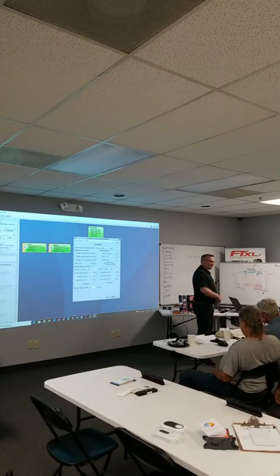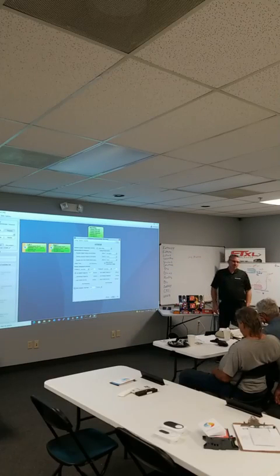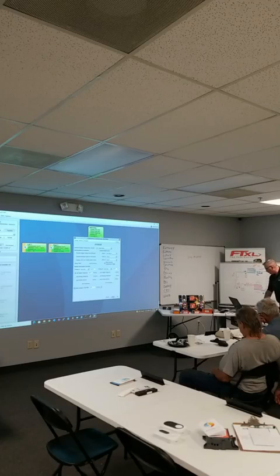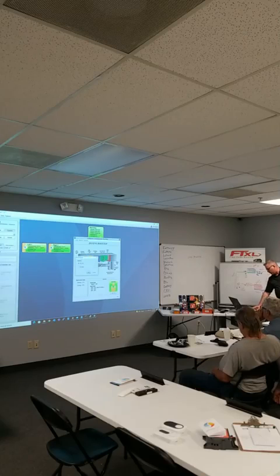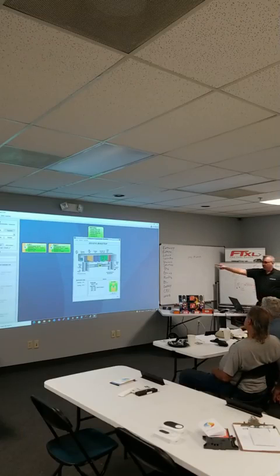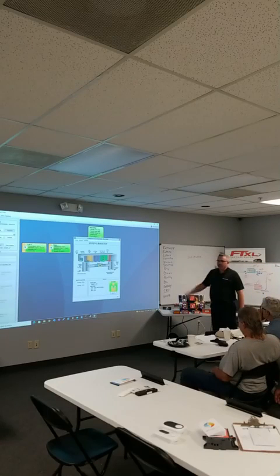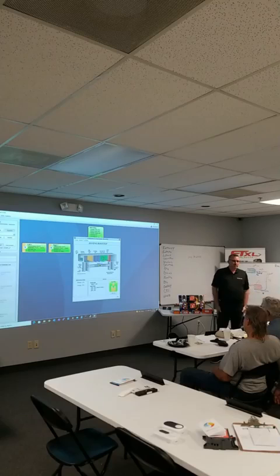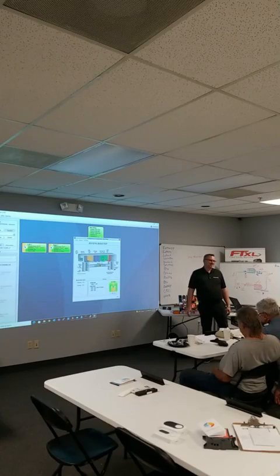I said, but what I need you to do now is go to your bypass damper. Something that I didn't show you guys is that from the graphic, you can right-click on an object and override it. So I did the same thing with this bypass damper. Here it's gonna flash at us. I overrode it, 25%, duct pressure didn't change. 100%, didn't change. I said, man, are those things even hooked up? He said, man, Tony, how'd you know that's not working? I said, your duct pressure's not changing, man.